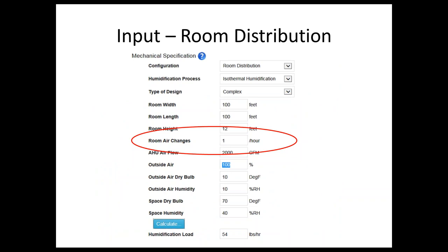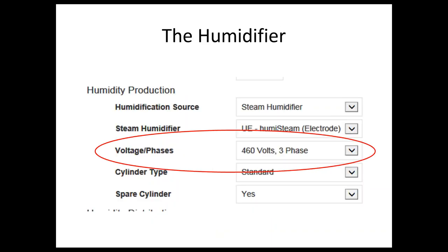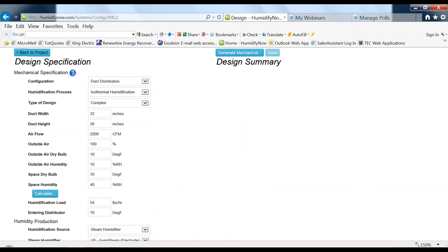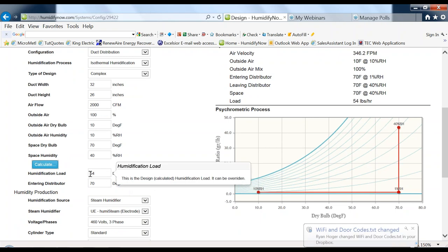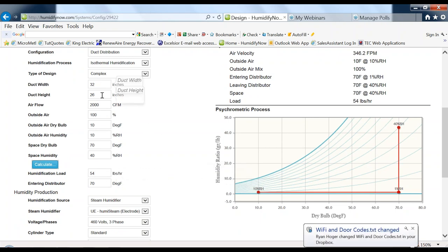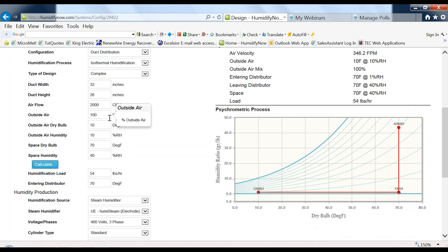For room distribution, the program asks for room height and room air changes, and it will figure out from the airflow or air changes per hour what the humidification load is. In one calculation example: duct size 32×26, airflow 2,000 CFM, 100% outside air, outside air dry bulb of 10°F and 10% outside air humidity. If you go to 50% outside air, the load would be less, of course.